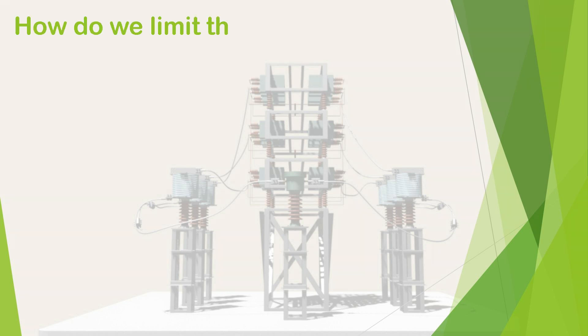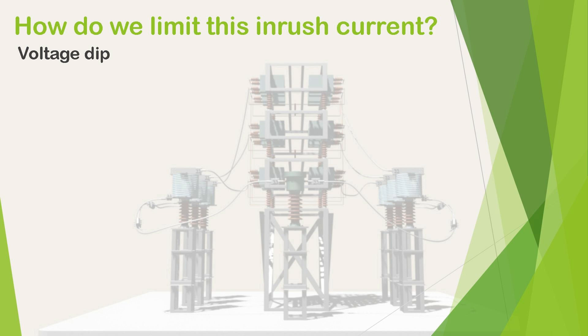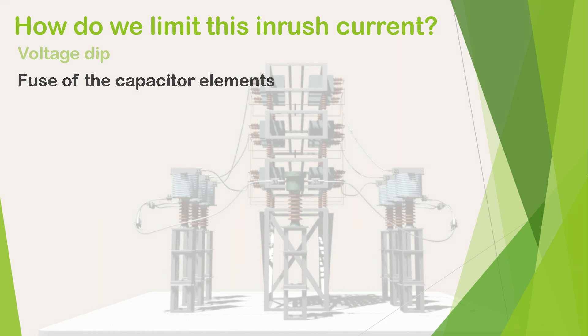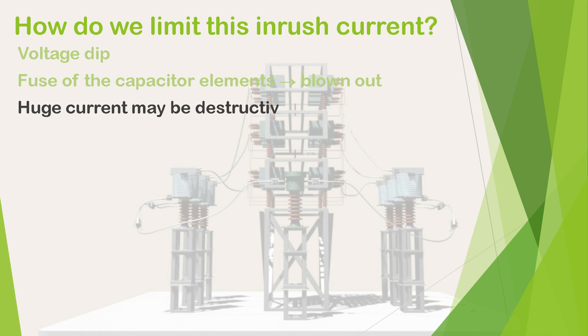How do we limit this inrush current? Otherwise it will create problems in the system. Because of this huge current flowing through the system, the voltage of the system suddenly dips. Due to this voltage dip, the relay can actuate under-voltage tripping in the circuit, which may disturb the power system stability. Also, due to this huge inrush current, the fuse of the capacitor elements inside the capacitor units may be blown out, and this huge current may be destructive for the capacitor bank itself and for other equipment connected in the power system.